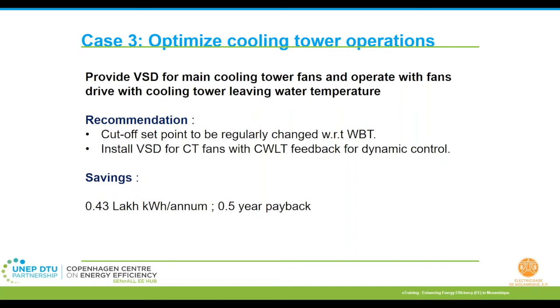If my cooling water temperature is 26.5 degrees, which is closer to my set point of 26 degrees, then my fan drive would probably be operating at about 65 to 70 or 80% of the full speed capacity. This way I would be consuming less power. This recommendation is also advantageous for accounting for seasonal or daily weather changes in atmospheric conditions. At times days can be hotter and nights can be colder. So they were able to achieve savings of about 0.43 lakh units per year with a simple payback of less than a year.